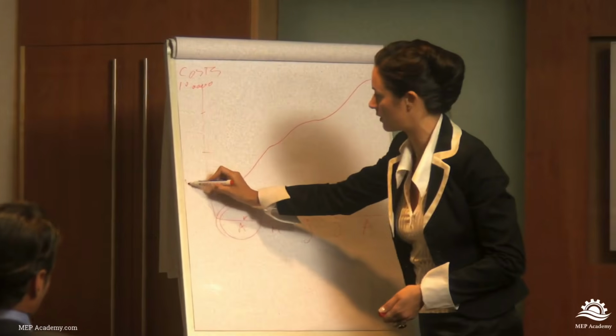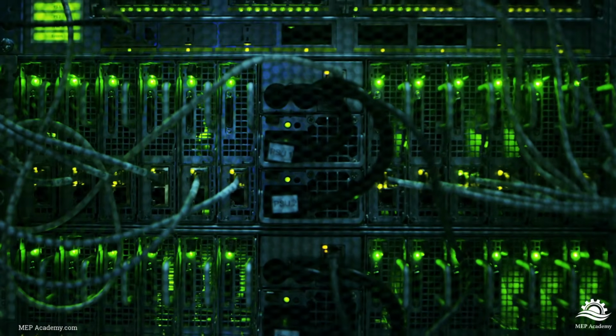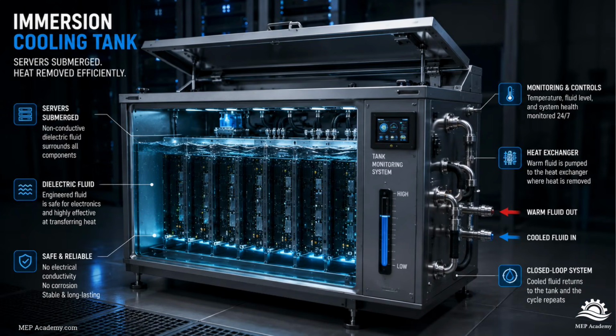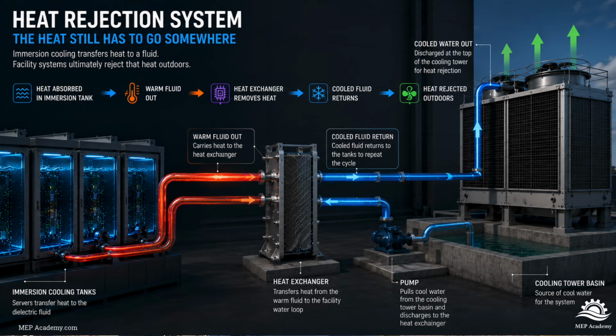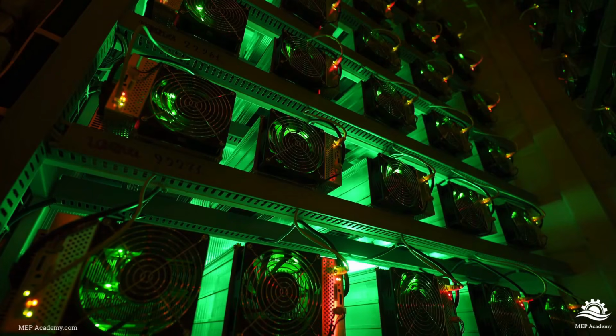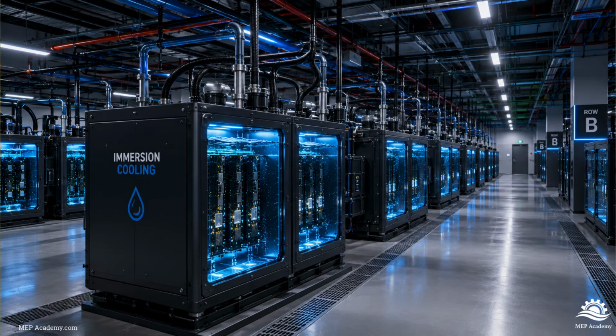So, let's summarize. Immersion cooling does not cool the room. It cools the servers directly. Servers are submerged inside a non-conductive dielectric fluid. Heat transfers into that fluid. The fluid carries the heat away. Then facility mechanical systems ultimately reject that heat outdoors. As AI continues pushing rack densities higher and higher, immersion cooling may become one of the defining technologies of the next generation of data centers. And perhaps the strangest part of all, the future of computing may involve intentionally putting our most expensive electronics into a bathtub full of liquid.